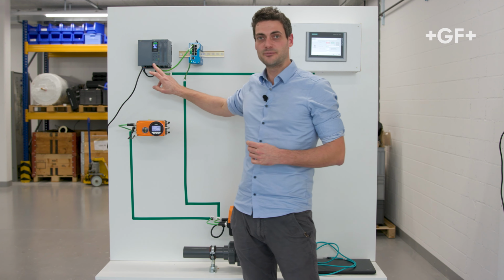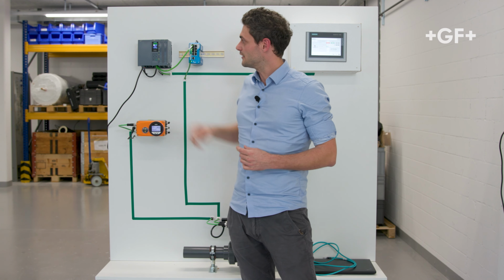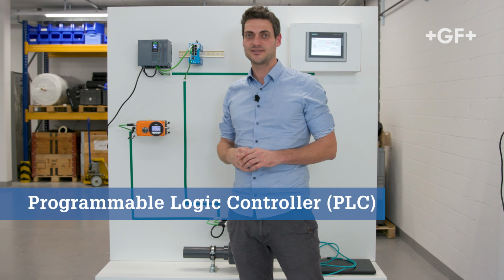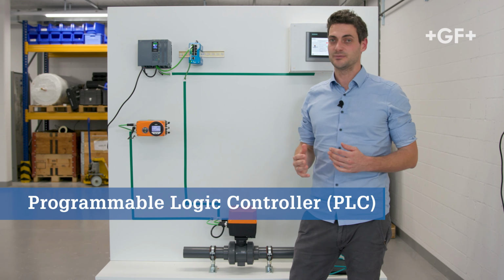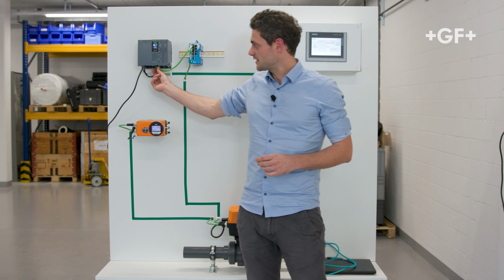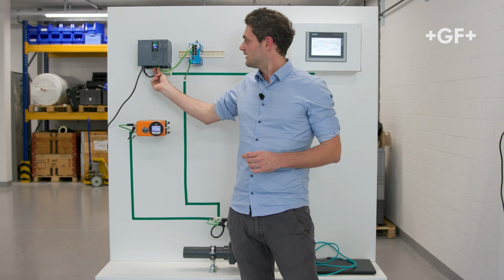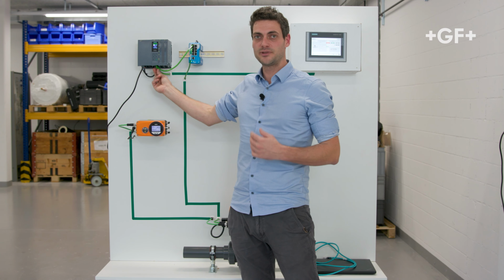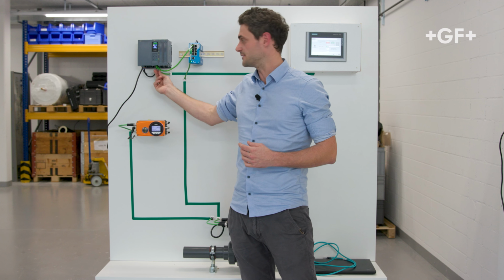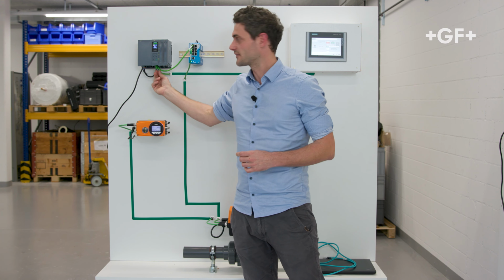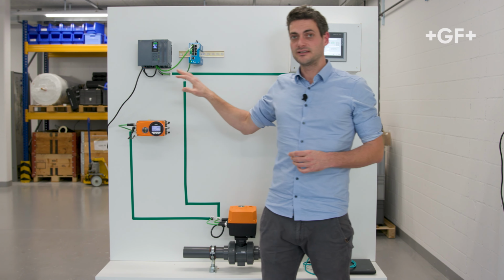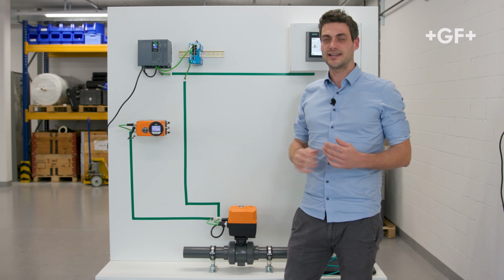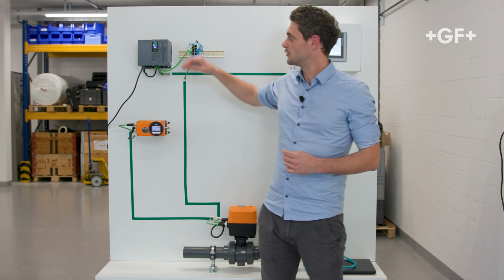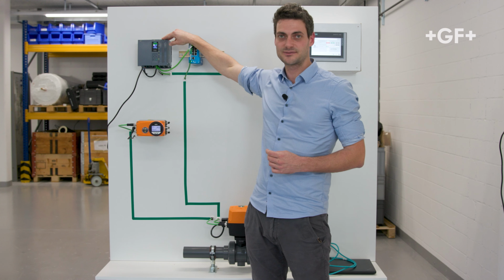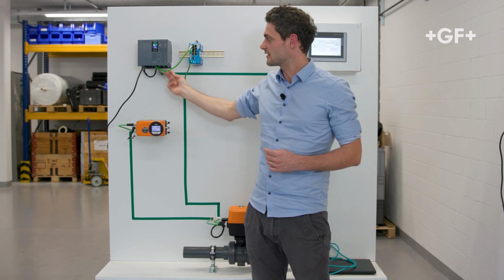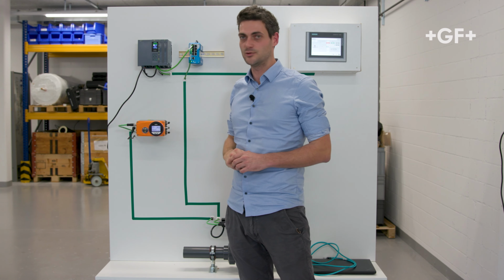Let's start here with the PLC. In this case, I've decided to use a Siemens PLC of the 1500 series, which is quite common in the market. This PLC comes directly with two Ethernet ports, which means it's directly possible to speak this Profinet language to the PLC. No additional interface cards needed. To set up an Ethernet network without analog sensors, it's not even needed to have input-output cards. Even though they are connected here to the PLC, no devices are connected to those I/O cards.